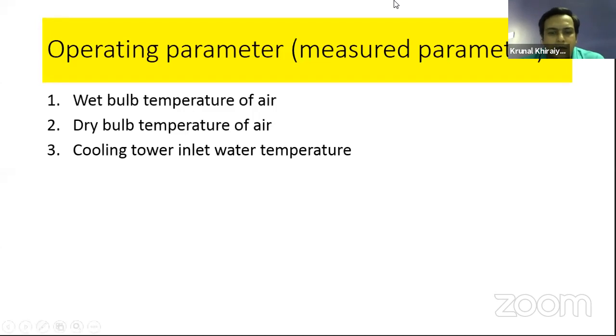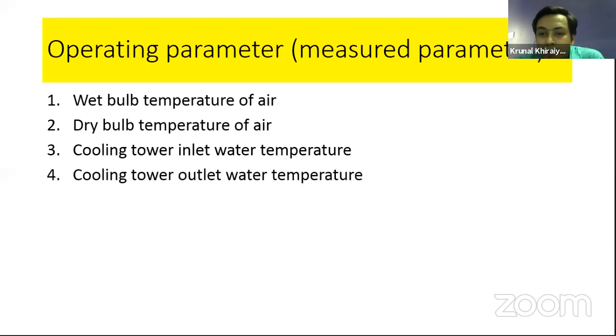Then cooling water inlet temperature. Which kind of device is used? Please, audience, respond. Cooling tower inlet water temperature: how do you measure the temperature of cooling water which comes from heat exchangers, chemical jacketed vessels or any heat sources which are supplied the cooling water? We use RTDs or different types of devices for the cooling water temperature measurement. Yes, I get the response. Bhavin Makwana, temperature gauge. Yes, RTD, very good. So using these different temperature devices as per the requirement of your resolution, you can use any kind of device. A PT100 is also one good sensor, available with 4-wire, to measure the temperatures.